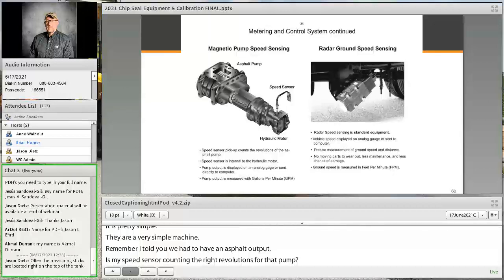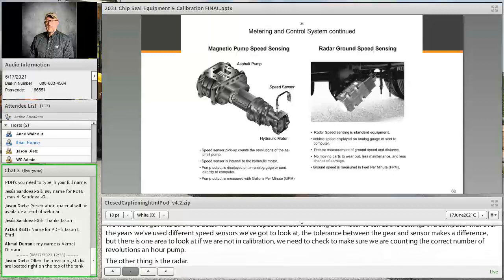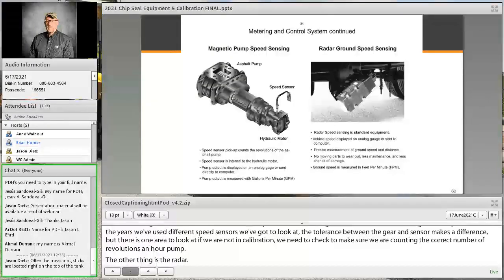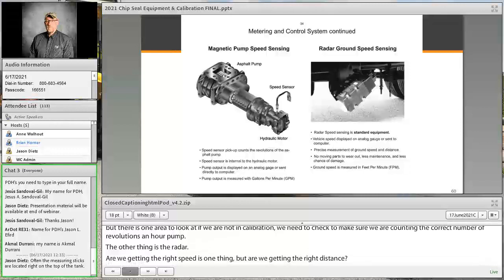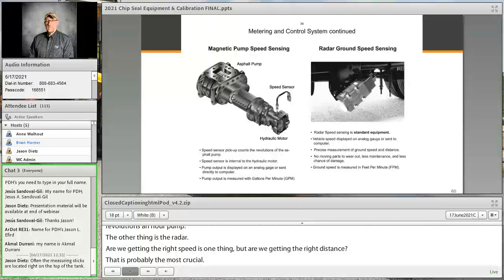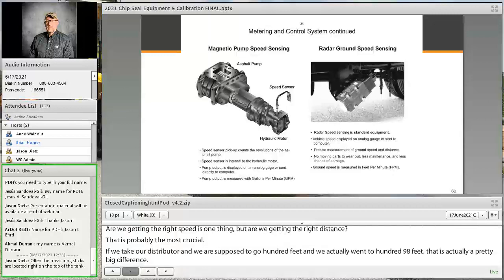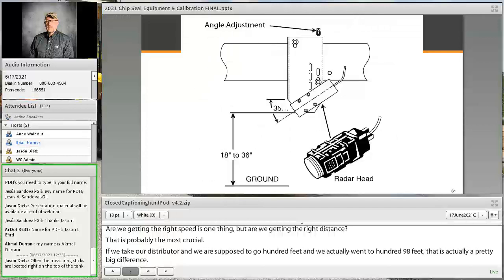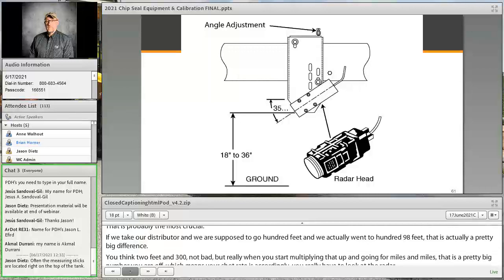The other thing is the radar. Are we getting the right speed, but more importantly, are we getting the right distance? That's probably the most crucial. Because if we're supposed to go 300 feet and we actually went 298 feet, that's actually a pretty big difference. You think 2 feet in 300 isn't bad, but when you multiply that up over miles and miles, all of a sudden that's a pretty big number we're off, which means your shot rate is off accordingly. So you really have to look at the radar, make sure it's set at the right angle, the lens is clean, all that stuff we can tell you about how to check.